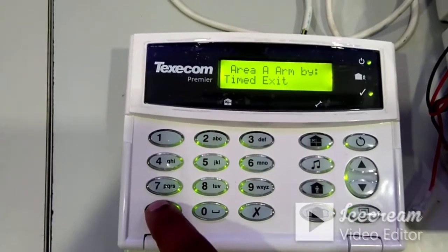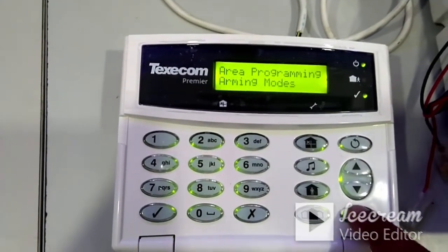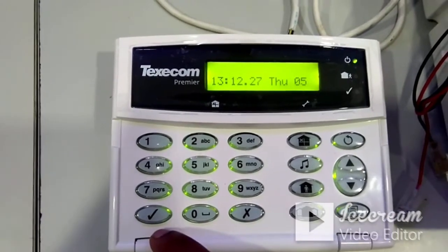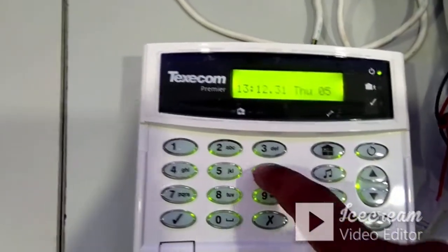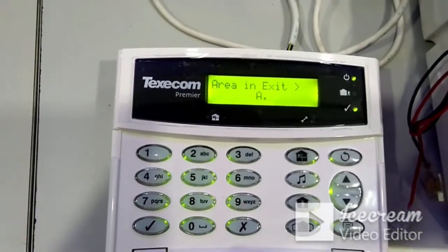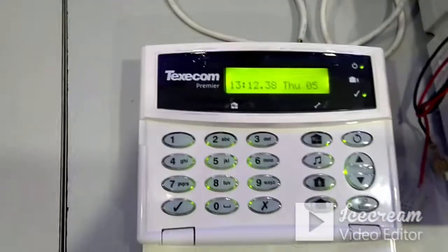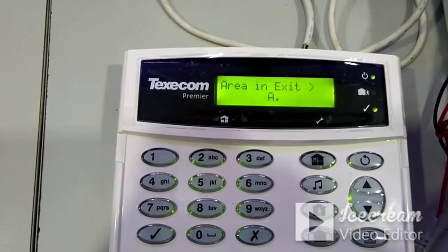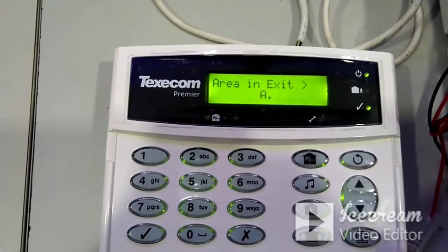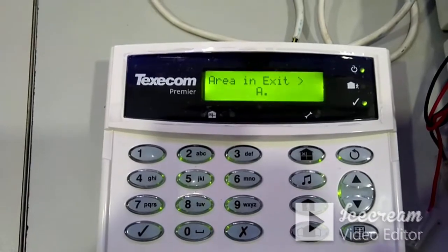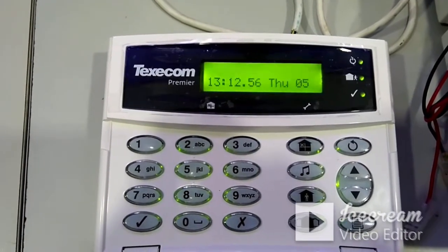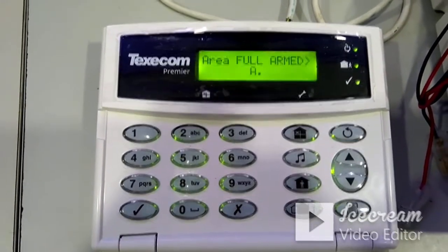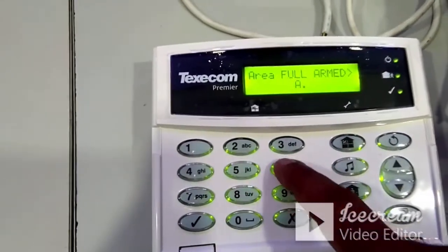These are the basic programming steps for this panel. To arm the panel, enter the default user password 5-6-7-8. The panel gives an exit delay warning tone — since 20 seconds was set, this notification plays for 20 seconds while you exit. After the delay, the panel is fully armed. If any zone activates, the sounder triggers immediately. To disarm, press 5-6-7-8, confirm 'do you want to disarm,' and press Yes.